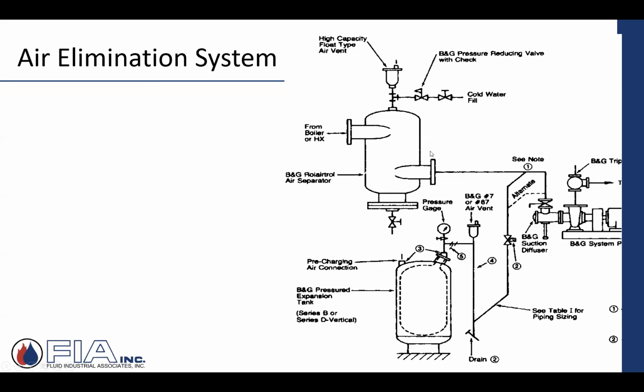And what's really good about this orientation here is this is the discharge coming out of that air separator right into my suction diffuser, right into the eye of the impeller, right into my pump. So I'm providing nice air-free water into the pump. Perfect. It's exactly what you're trying to do when you're sitting there designing that system. It all comes together. I got air separation in between the air separator and the pump. Here's my compression. Here's my expansion tank. These are just little piping details. We'll get into a little bit later on, like I said, in the following weeks on how to install it. But that's a very good installation of an air elimination.